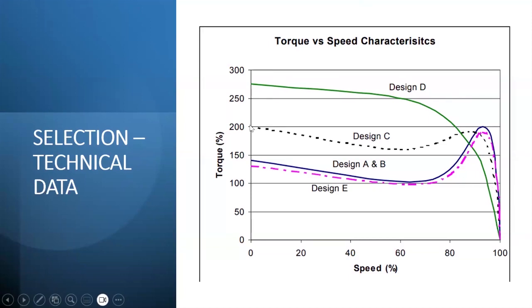But let's look at a design class C. For a design C type, the motor will have a starting torque of about 200% of the rated torque. But as the motor approaches its full load speed, the torque is higher. Look at the screen for the design type C. You see the torque is higher as the motor even approaches its full load speed. So in such application, if you know you'll be facing dynamic torque, which will require the motor to have enough torque to do the work, you specify the torque or you inform the manufacturer the application you are going to use. Normal general purpose motors are design type B.